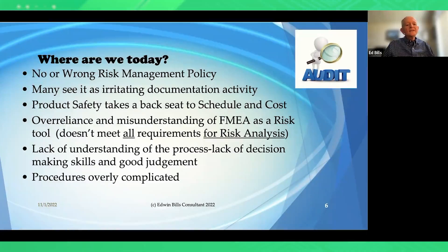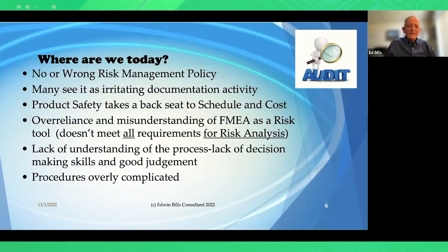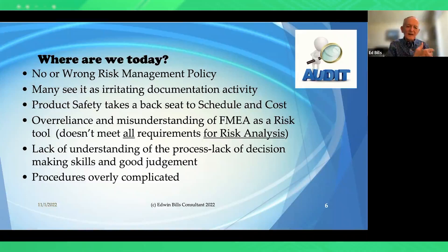ISO 13485-2016 Clause 7.3.3C says that the outputs of risk management are design inputs, meaning risk management activities must be completed prior to design input — not later on, as many are doing. There is either no or a wrong risk management policy in many cases. Top management needs to have established the risk management policy, which tells you what kind of acceptability criteria you'll develop.